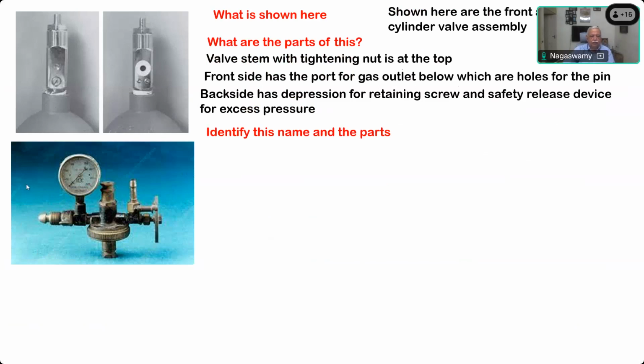Similarly, if it's a direct pipeline supply, that will also be reduced to 14 to 15 psi, because the pressure which should reach the flow meter assembly is only 14 to 15 psi. Please remember that. Whether it is 2000 psi directly coming from an attached cylinder or 40 to 50 psi coming from a central pipeline supply, this pressure regulator has to reduce the pressure to 14 to 15 psi, and these are the further connections going to the flow meter, and this is one going to the emergency outlet.